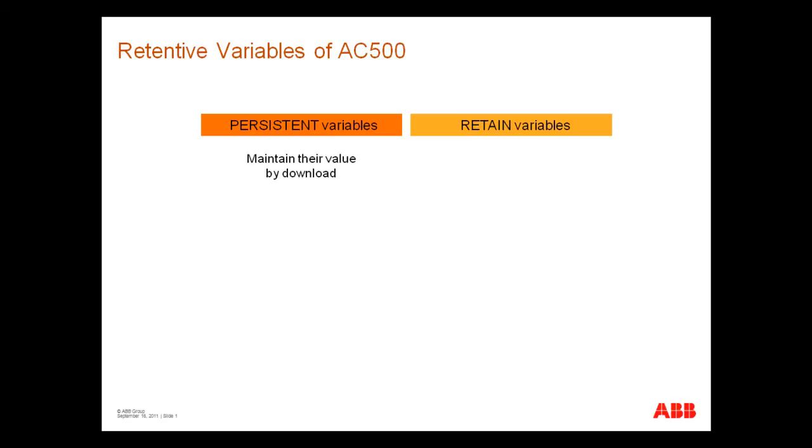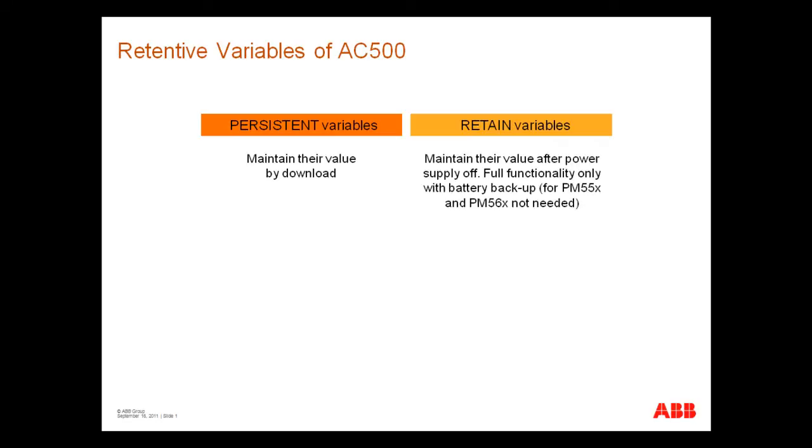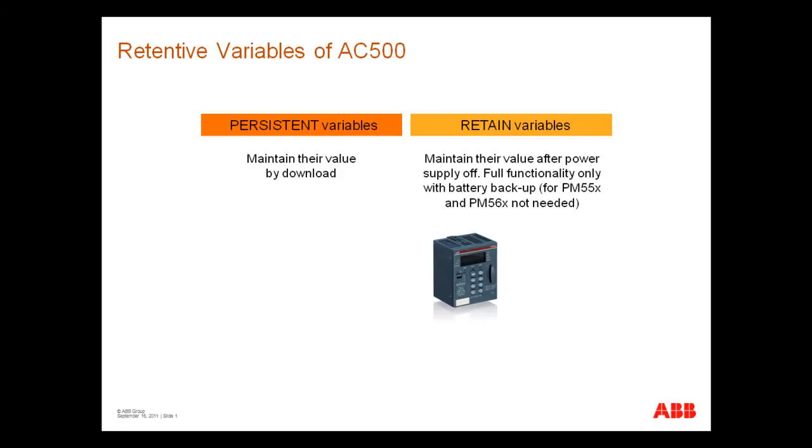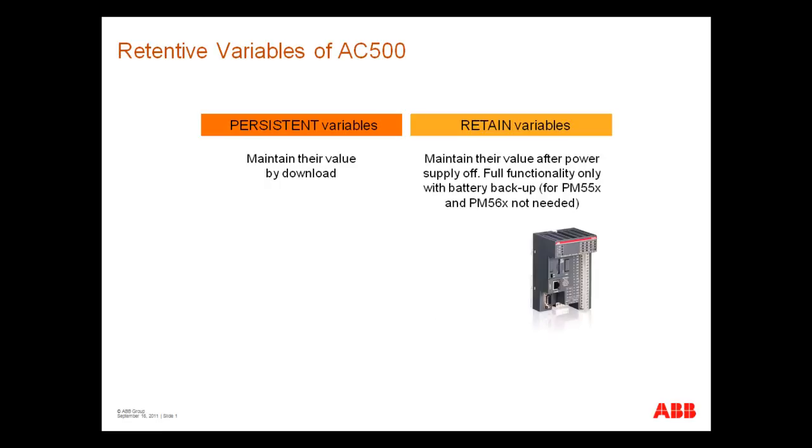For CPUs of type PM57x, PM58x and PM59x this functionality is given only with battery. For types PM55x and PM56x the battery is not needed. The retentive variables are stored in the flash EPROM.